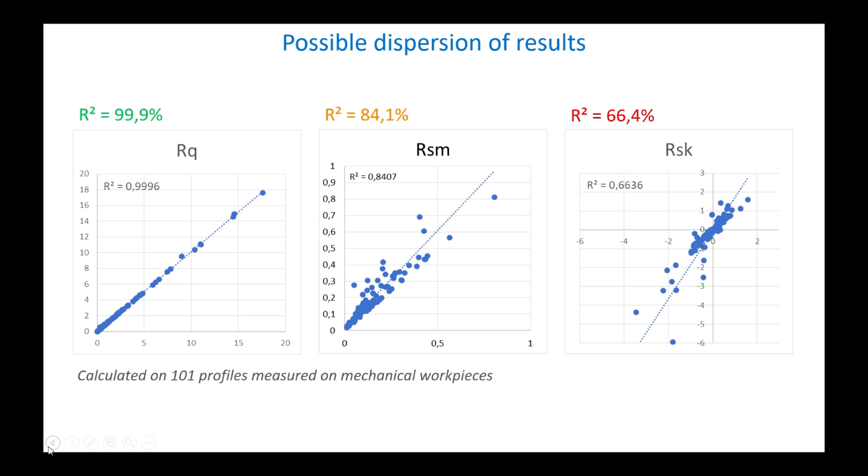When we compare parameters from the two standards calculated on the same profiles, we note discrepancies which are linked to differences in the definition of the parameters and to changes in the process of preparing the primary profile. Some parameters are particularly sensitive, such as RSK or RKU. Others barely change like RA, RQ, or RDQ. It is therefore recommended to check your data and recalculate the parameters with the new standard to see if it is necessary to adjust the tolerances on drawings. However, this should not prevent industry and research from adopting the new ISO 21920 standard for new projects.